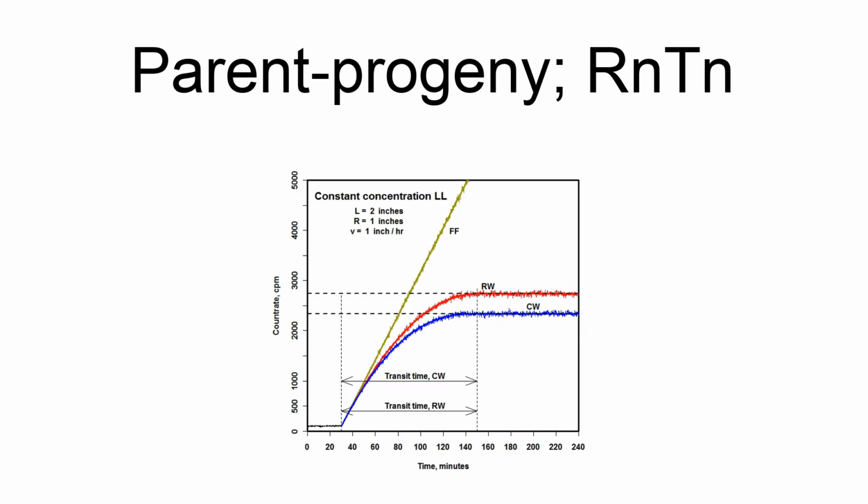There are situations in which a nuclide deposited on the CPAM filter decays into another nuclide, and that second nuclide remains on the filter. This parent-progeny or decay chain situation is especially relevant to so-called radon-thoron, RN/TN, or natural airborne radioactivity. The mathematical treatment described in this article does not consider this situation, but it can be treated using matrix methods, see Ref 11.